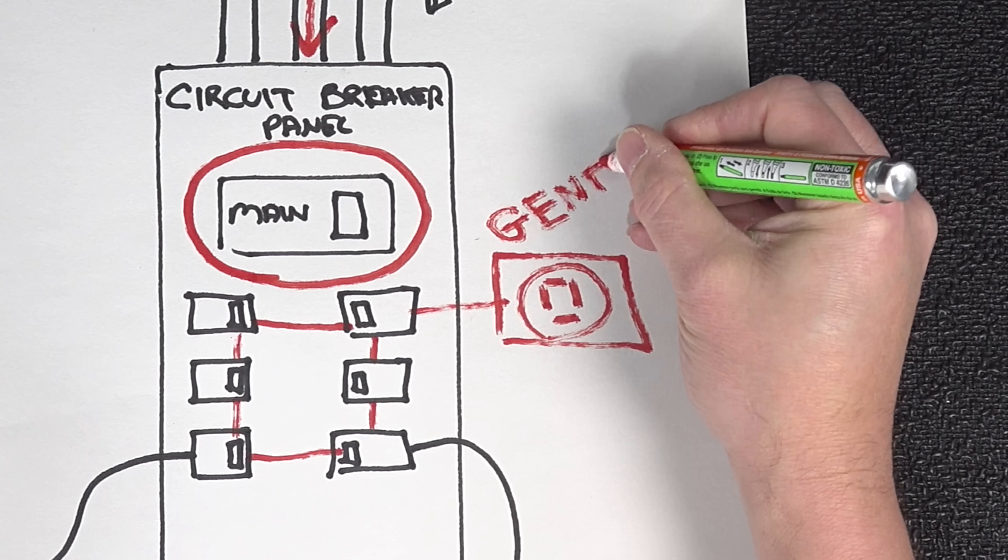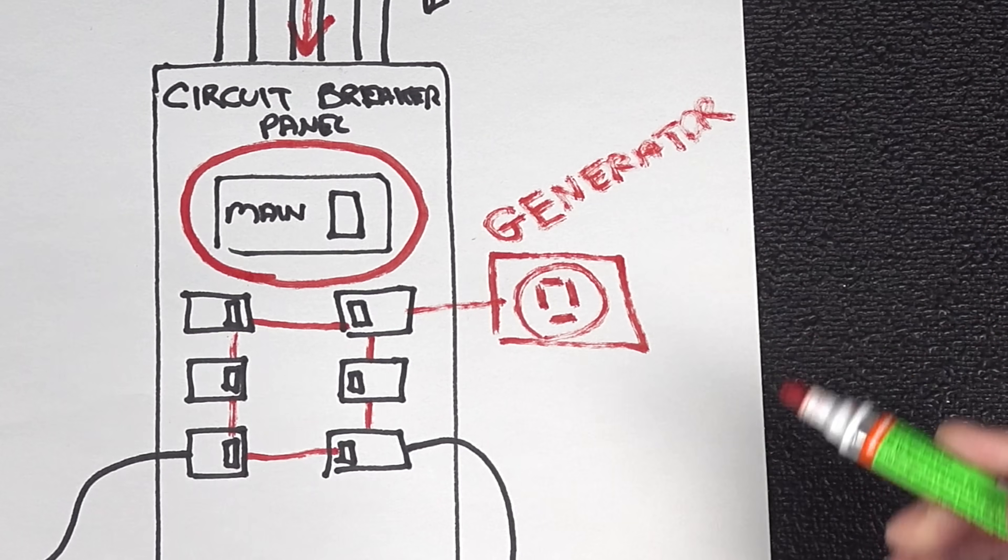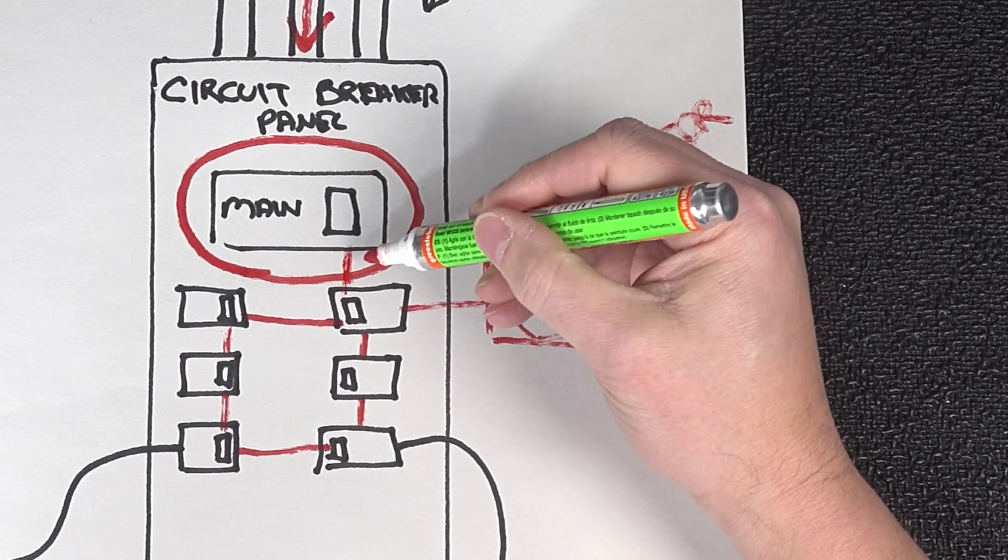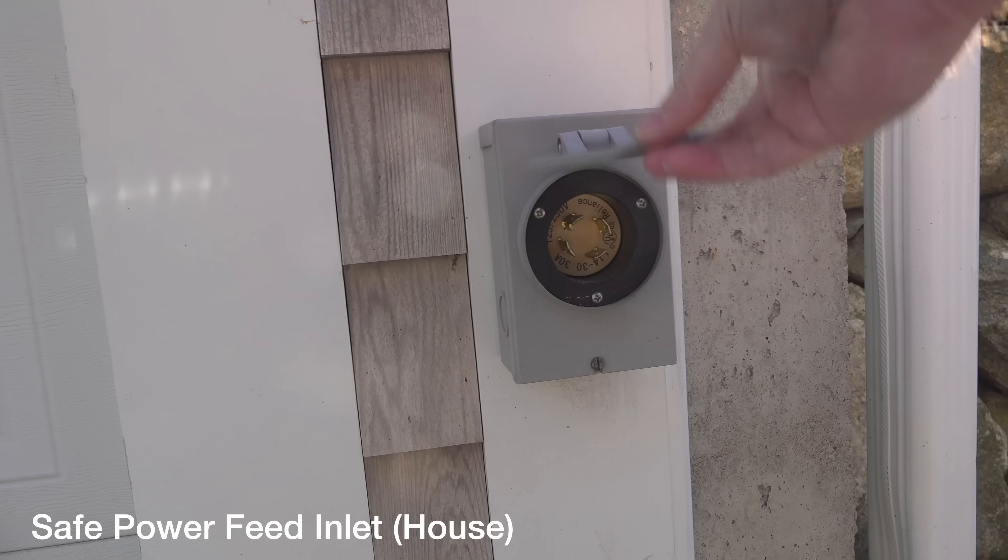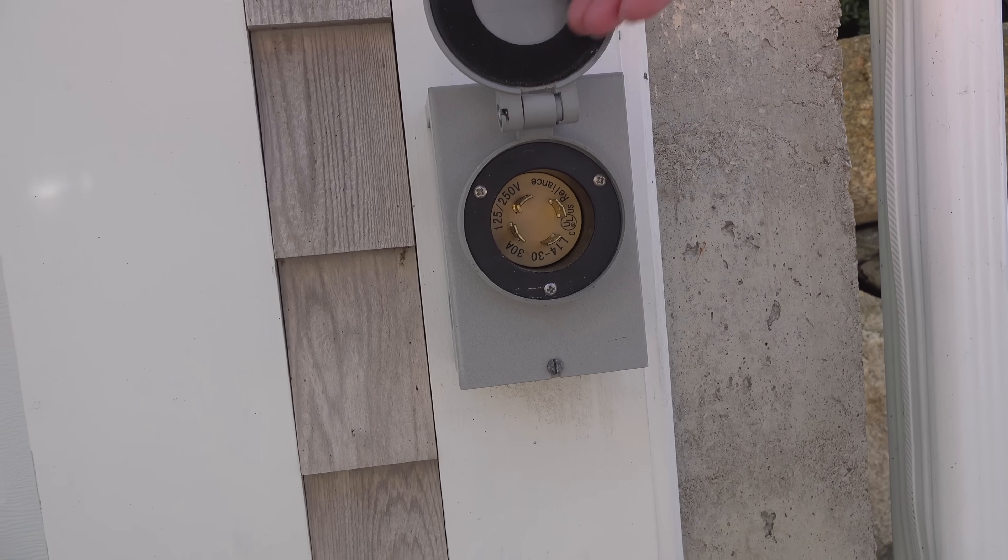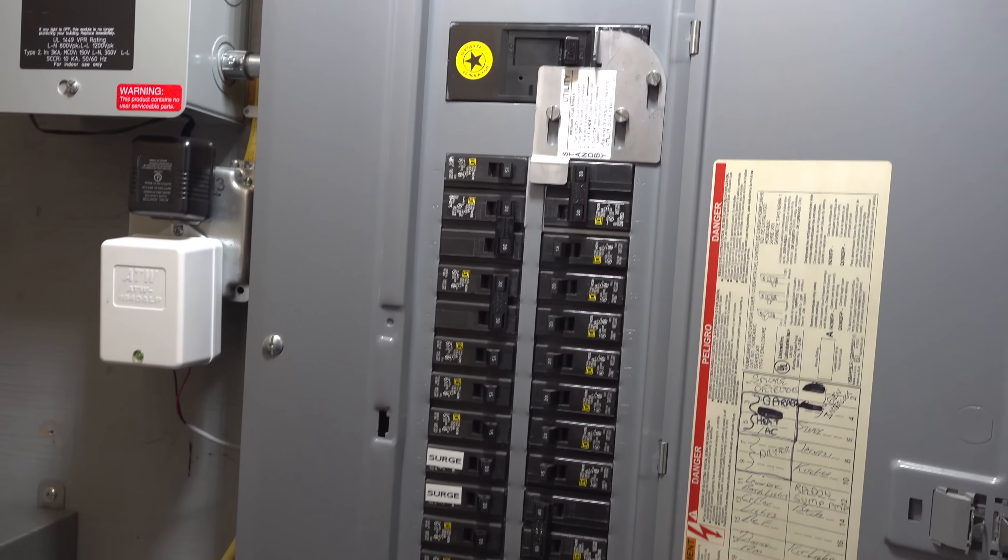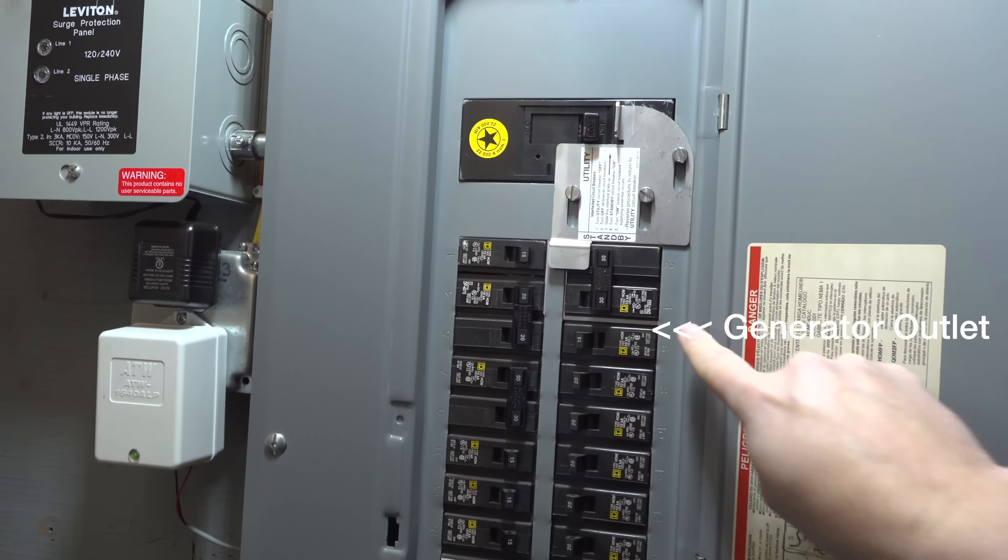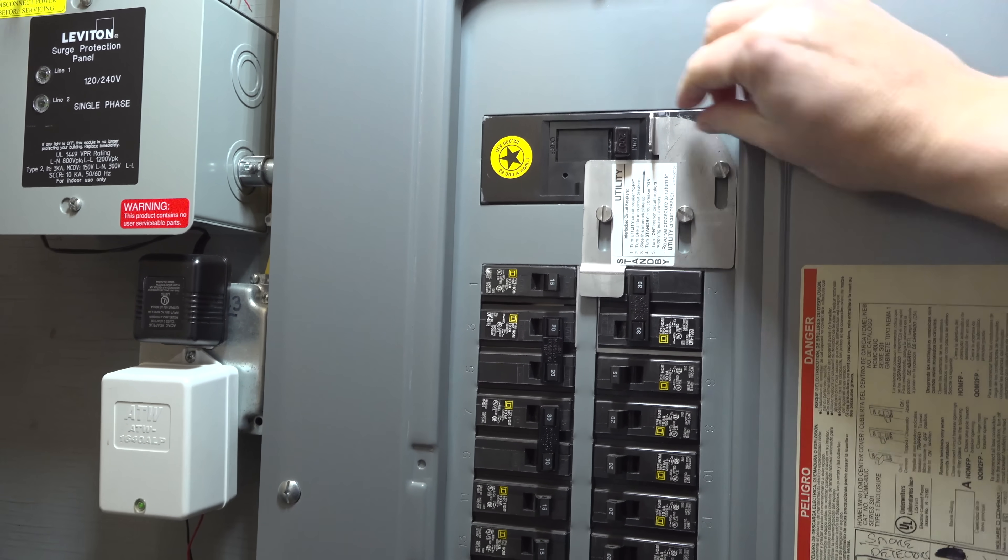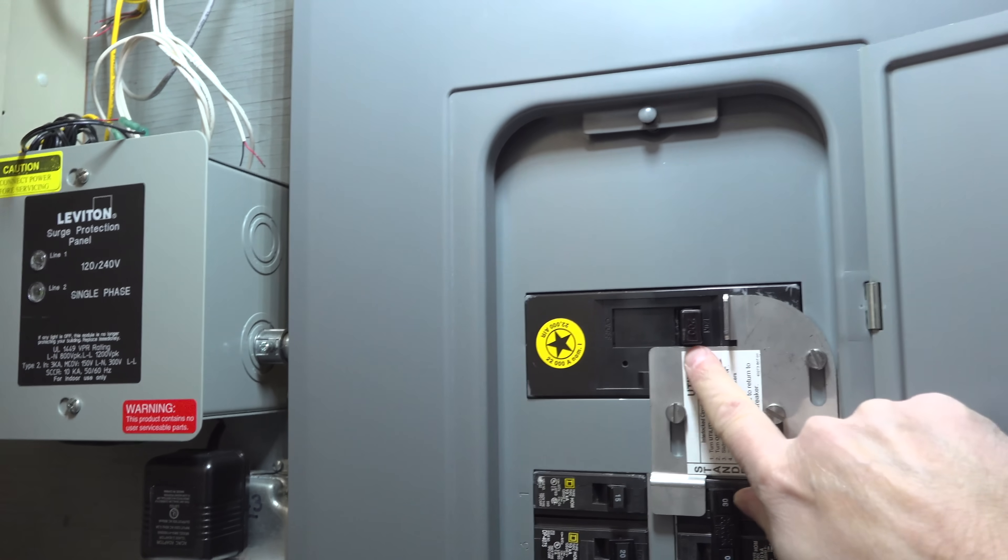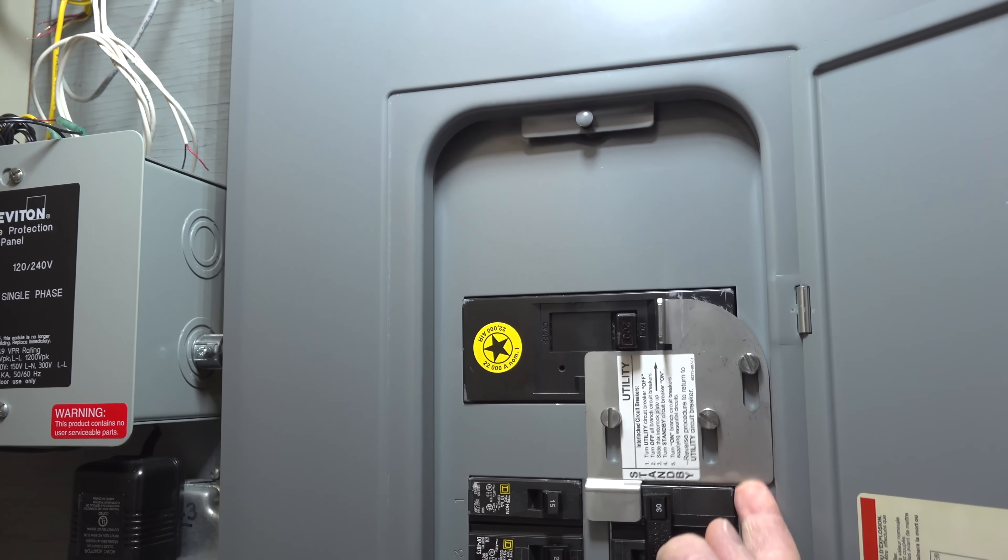But fortunately there are a couple of legal safe ways to connect your generator to your house that takes all of this worry away. Now the first one is to use something called an interlock. You'd install an outlet like this off of a special circuit breaker on your panel and then you'd install this small metal plate. And all this metal plate does is ensure that the generator outlet and your main breaker cannot be on at the same time. So you either get to use your generator outlet or have your main breaker on. But this prevents you from doing any sort of backfeeding.